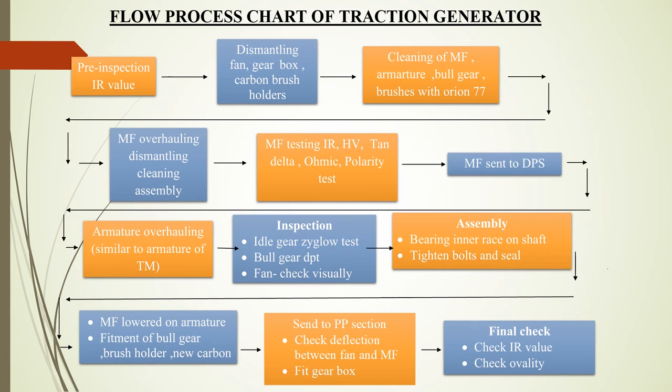After that, the Traction Generator is tested with tests like IR test, high voltage test, tan delta test, ohmic test, and polarity test. After that, the magnet frame is sent to the diesel POH shop. Armature overhauling is also similar to the Traction Motor. All these parts are then sent back to the Traction Generator section. An inspection of other parts happens wherein a Zyglow test is done on the idle gear, a dye penetration test is carried out on the bull gear, and the fan is checked visually.